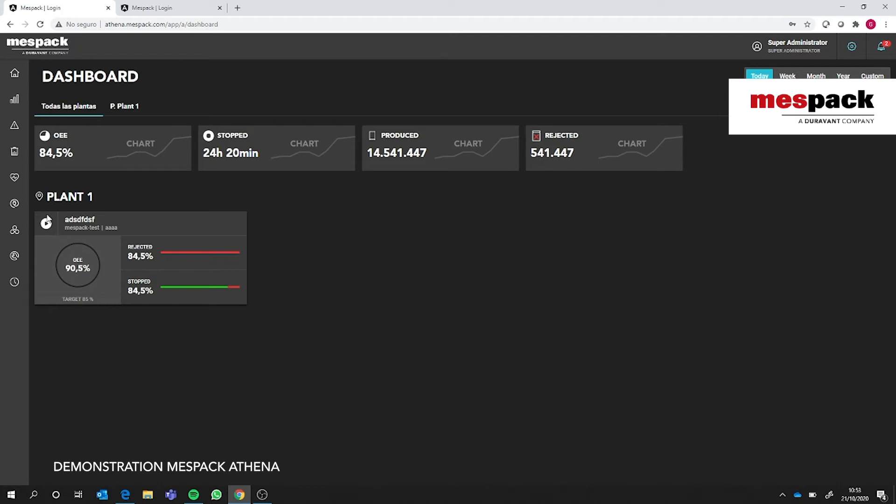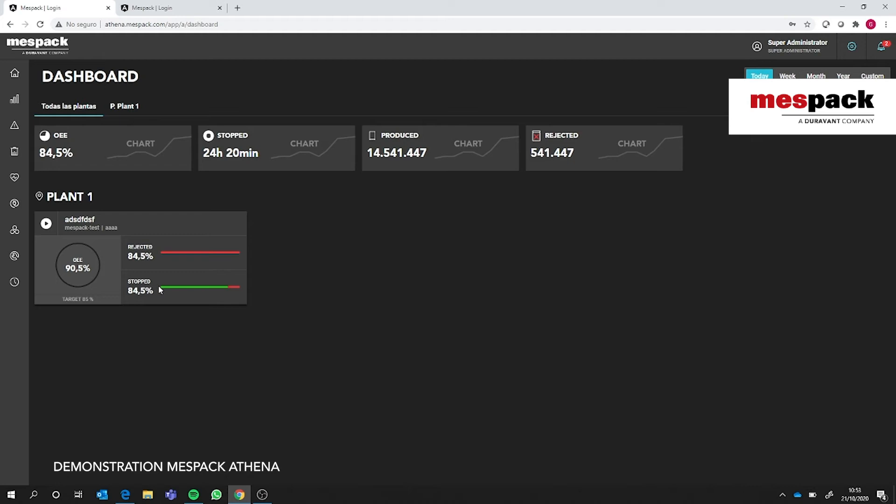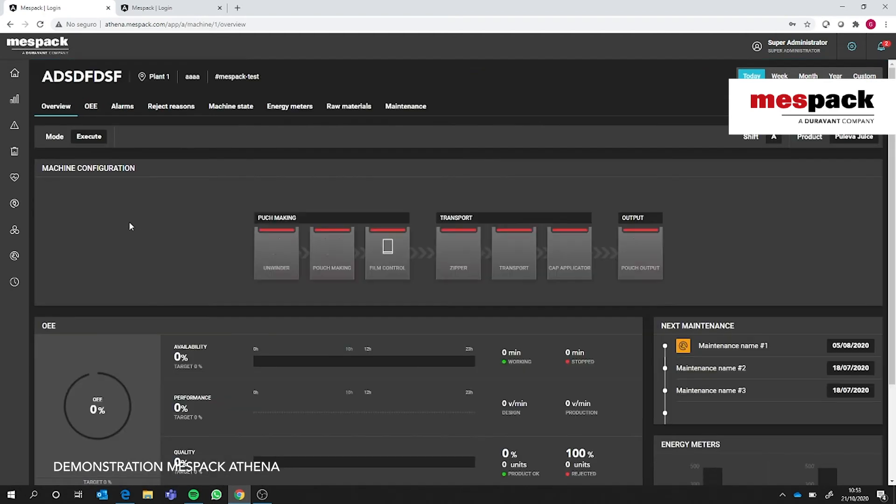We can see the most relevant data for that machine. On the top left corner we have an icon showing if the machine is running, stopped, or paused. We have a big display showing the OEE of the machine which would change colors depending on the set target. On the right side we see the rejected ratio and the stop time ratio. Ideally everything would be fully green—100% runtime and 100% accepted pouches. This bar would turn red depending on whether we have more stop time or more reject ratio.